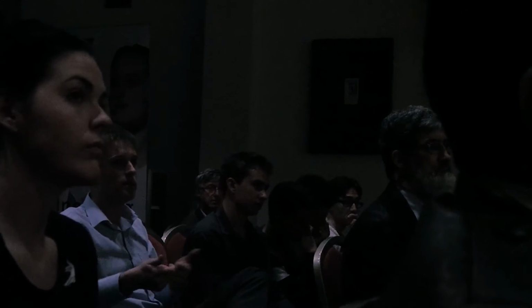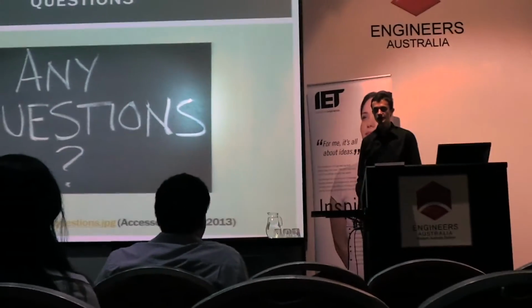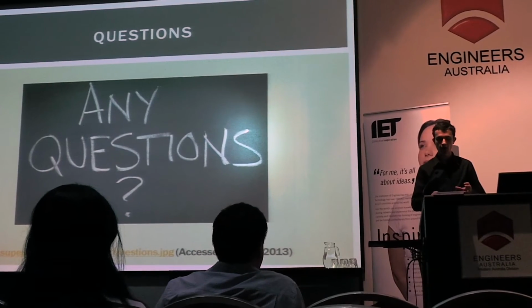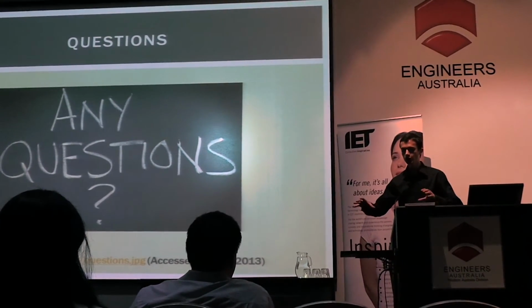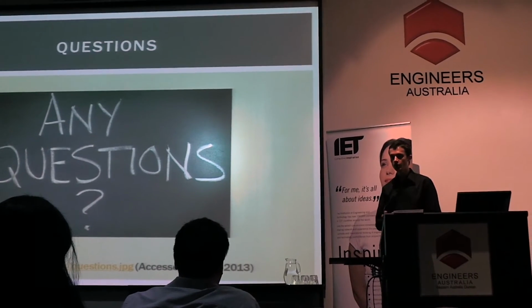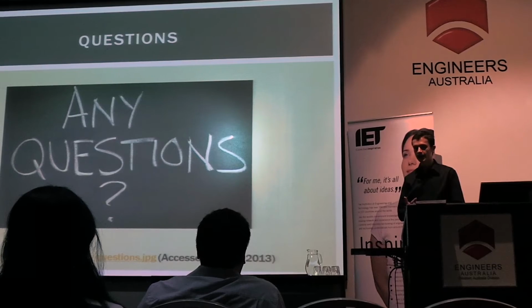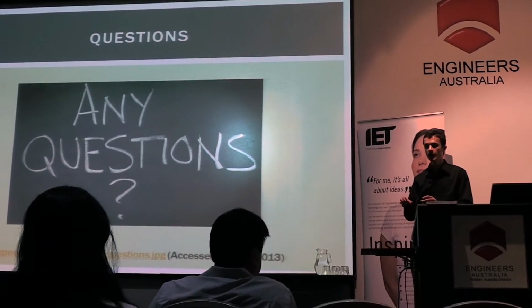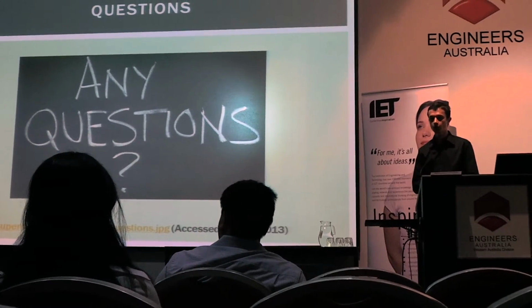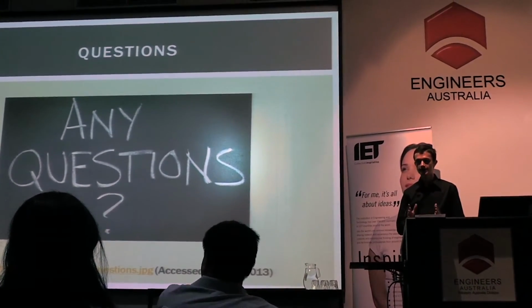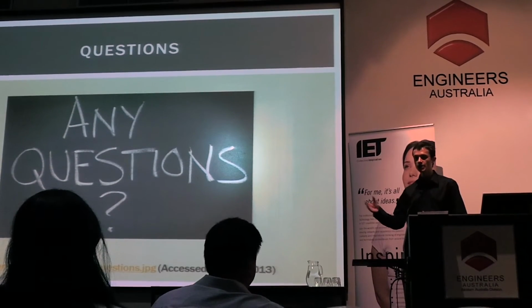How close would the special protection system be to the actual faults? I imagine that this sort of control signal has to travel to somewhere to perform the correct action, and then with such small periods of time, I'm wondering if the speed of light becomes too slow. Yeah, speed is a major concern with SPS. Unlike conventional protection schemes or normal controls, it won't go through the Rio Tinto Operation Centre. It will be placed locally on the power system, and as such, when you're monitoring the bus bars or the loads or even the generators, we can access those values in real time. For conventional protection, usually we're good if it's in 100 milliseconds. So if the fault is, say, somewhere between 100 and 140, the SPS should be able to do its job.